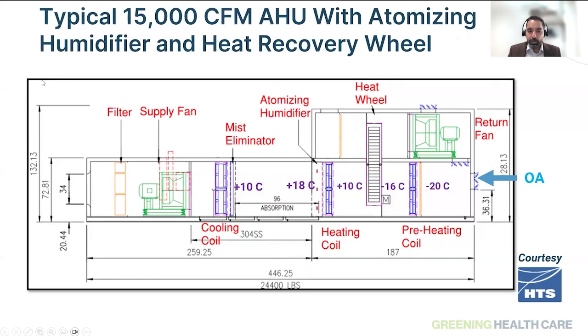Now, if you are in that position where you're looking at replacing a similar unit, what does that unit look like if you were to replace that steam humidification with adiabatic humidification? This is what our typical unit of 15,000 CFM looks like. You will notice that two things change with this unit. One is obviously that the length of the unit increased, given that you need more absorption length for adiabatic humidification, and the weight of the unit increased as well, for obvious reasons. So this unit is a selection where it not only recovers the heat with the enthalpy wheel, which is included in there, but also has an adiabatic humidification system along with it.